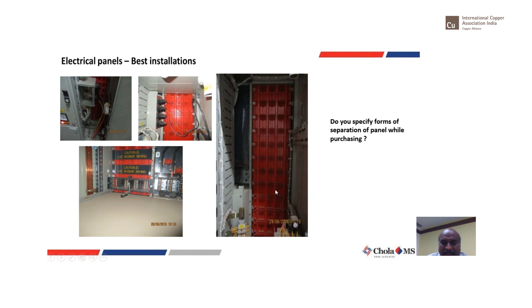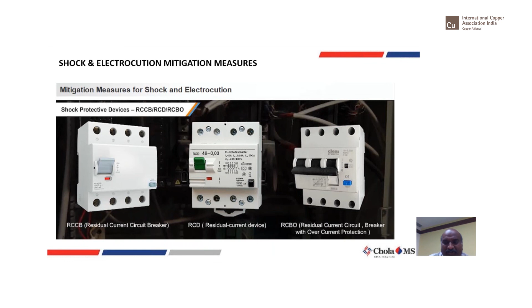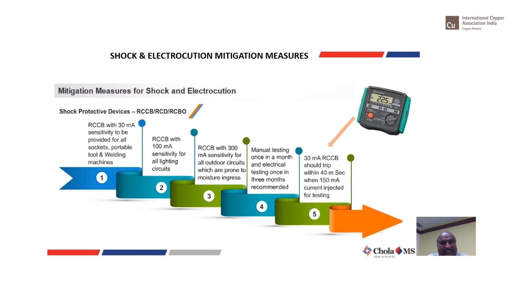Yes, you have these RCCBs and RCDs. Have them at their proper selections, 30 milliamps for human protection, and have them in the circuit so that they trip and protect. You cannot stand at all places and ensure that everything is fine. Provide these devices; at least these will take care and protect the shop floor and the people working in that area. So you might need an RCCB tester for 30 milliamps, 300 milliamps and 100 milliamps. CEA regulations also give clarity on where to use what. 30 milliamps is for human contact. Wherever you feel that unskilled labor is going to touch that equipment, please provide 30 milliamps. 100 milliamps can be used for lighting circuits, and 300 for high-mast light fittings or places where people will not have easy access. So please follow these norms.